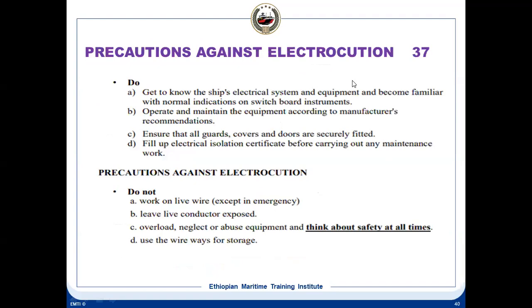Precautions against electrocution. What are the do's and don'ts? Get to know the ship's electrical systems and equipment and become familiar with the normal indications on the switchboard instrumentation. Operate and maintain the equipment according to the manufacturer's recommendations. Ensure all guards, covers and doors are securely fitted. Fill up the electrical isolation certificate before carrying out any maintenance work. The first thing is you should have proper isolation. That is very important. You should have a permit to work system and a risk assessment. These are the basic parts.